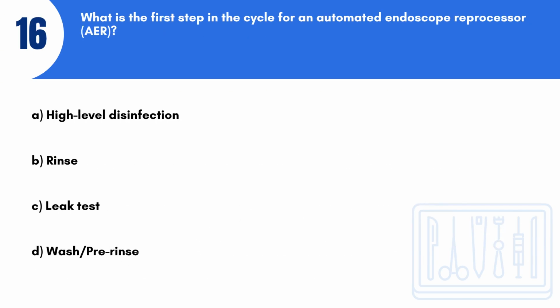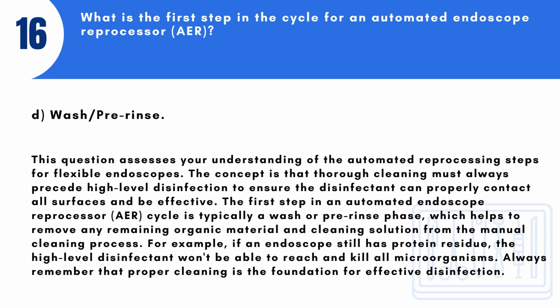Question 16. What is the first step in the cycle for an automated endoscope reprocessor, AER? A. High-level disinfection. B. Rinse. C. Leak test. D. Wash/pre-rinse. Answer: D. Wash/pre-rinse. This question assesses your understanding of the automated reprocessing steps for flexible endoscopes. The concept is that thorough cleaning must always precede high-level disinfection to ensure the disinfectant can properly contact all surfaces and be effective.